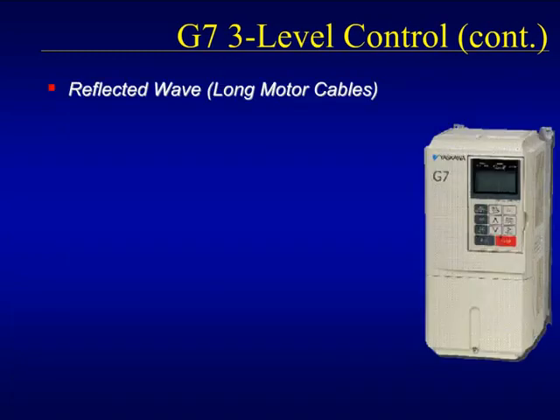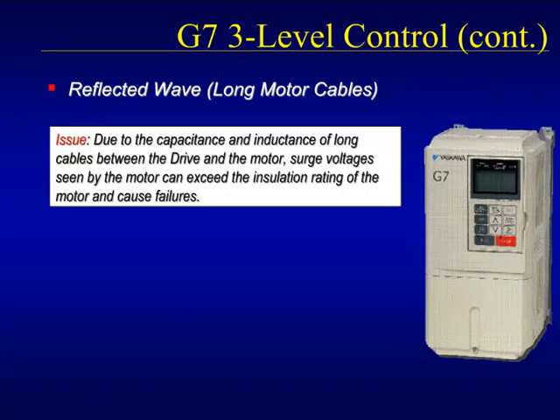Reflected wave is a phenomenon whereby voltage pulses, such as those created by PWM drives, are reflected back to the drive due to the characteristics of the cable coupled with the very high dV/dt of the pulses themselves. When the reflected pulse coincides with a new pulse, the effect is additive and the motor winding is subjected to peak-to-peak voltages that are more than twice the level of the drive's DC bus. These peak voltages can damage or destroy weaker motor insulation.